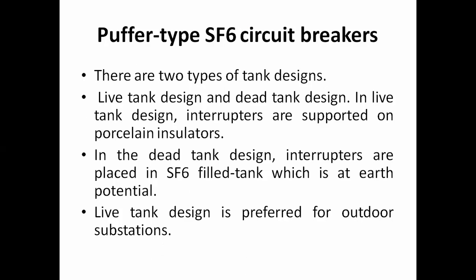In the puffer type circuit breaker, there are two types of tank design, the live tank design and the dead tank design. In the live tank design, interrupters are supported on porcelain insulators, and in the dead tank design, interrupters are placed in an SF6 filled tank, which is at earth potential. So this is about the puffer type SF6 circuit breaker.